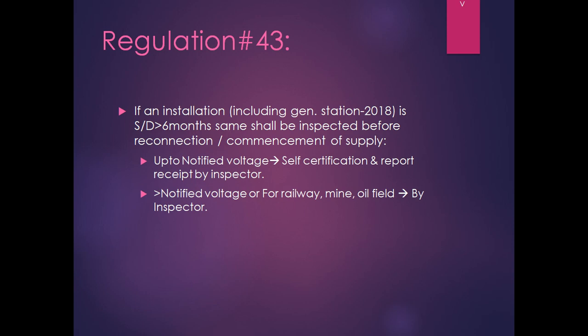This is a very common problem nowadays. Many installations are kept shut down for more than 6 months. Even though nobody wants to keep their installation shut down for a period of more than 6 months, it takes place. Suppose some major operation is taking place, it may take a time of more than 6 months. Then before recommencement of supply, that installation shall be inspected. Even if the last inspection has been done within 5 years, it has to be inspected once again if it is shut down for a period of more than 6 months.